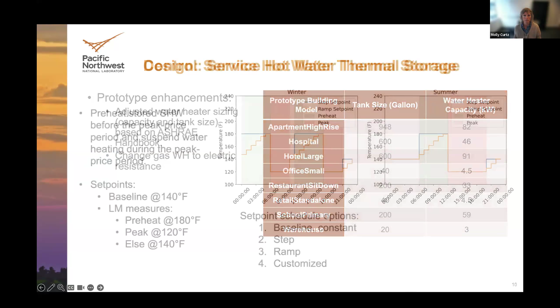Okay, so the control strategy that we looked at included 3 different controls approaches. All of them were fundamentally looking at, well, our baseline condition was 140 degrees all the time as the aquastat temperature for the tanks. And we looked at 3 different variants of that. One was to have a step control where we would have a 6-hour preheat period prior to the peak period, and we would heat the tank up to 180 degrees during the preheat 6-hour period. As soon as we reached the peak period, the aquastat dropped down to 120 to discourage the tank from firing or the element from engaging during that peak period. And then for periods that were not peak or preheat, we put the tank at the baseline 140 aquastat set point.